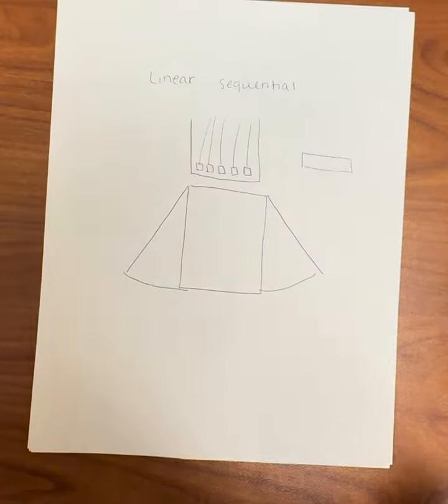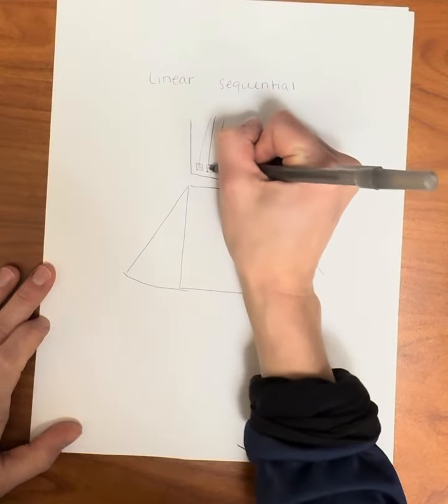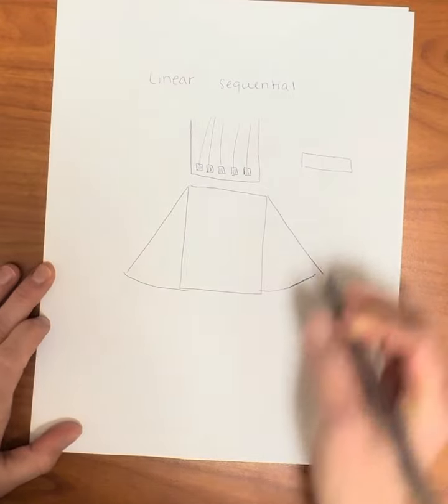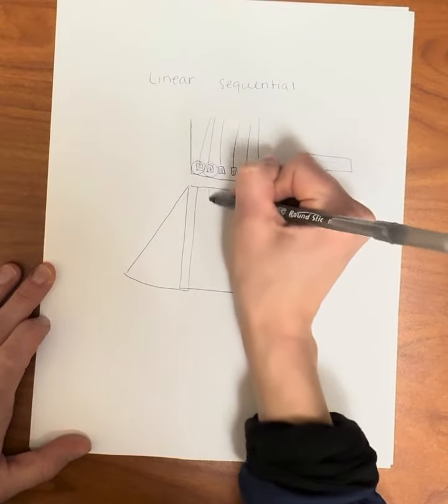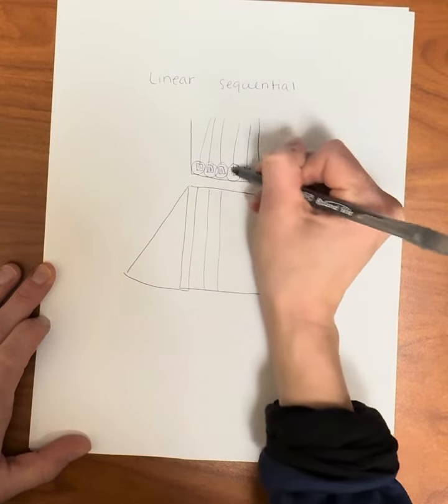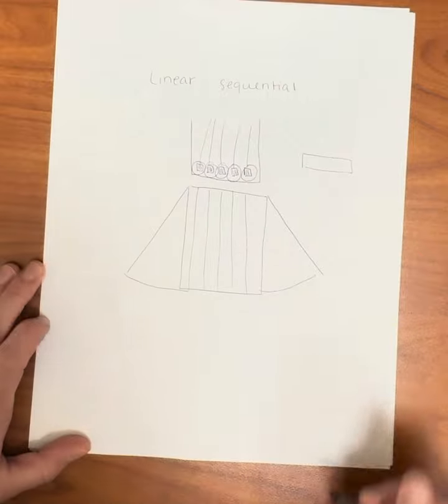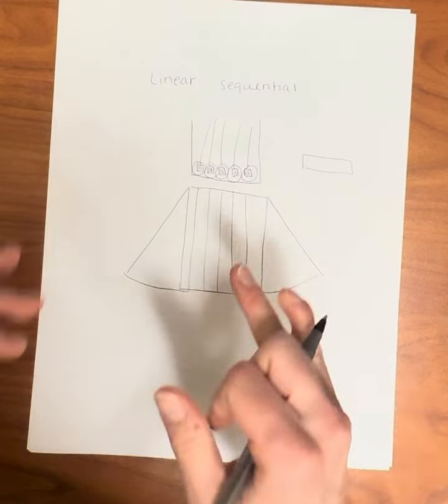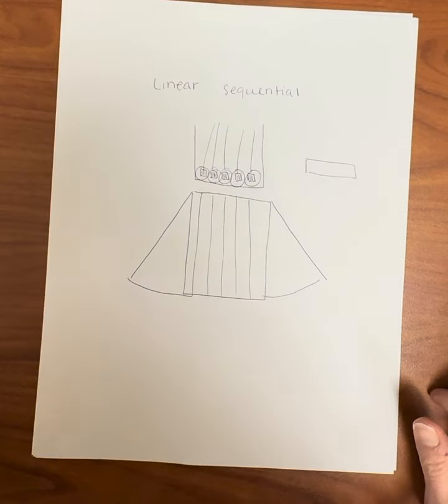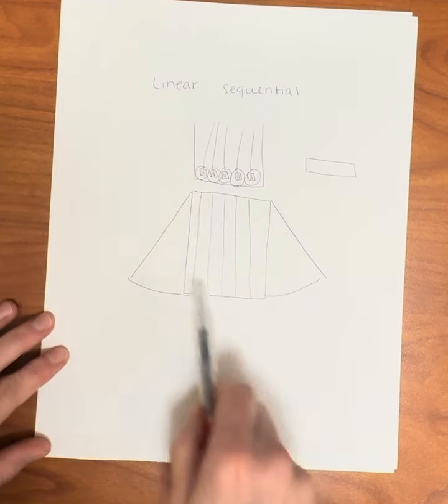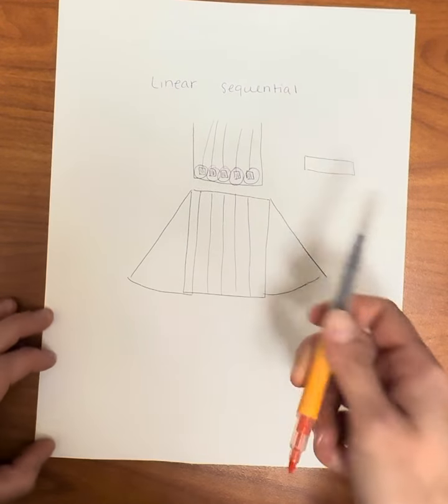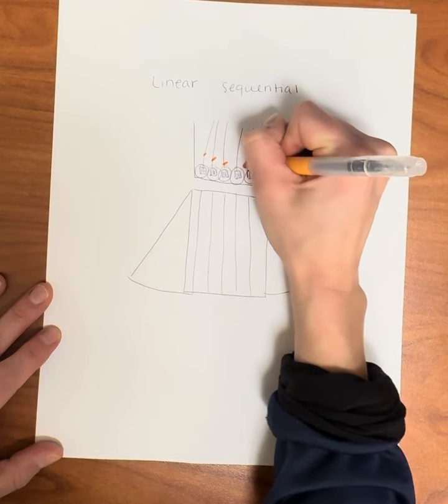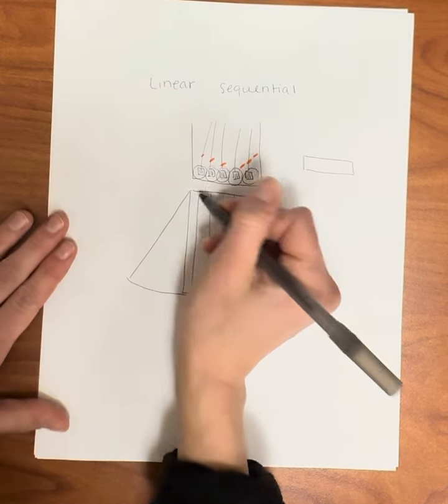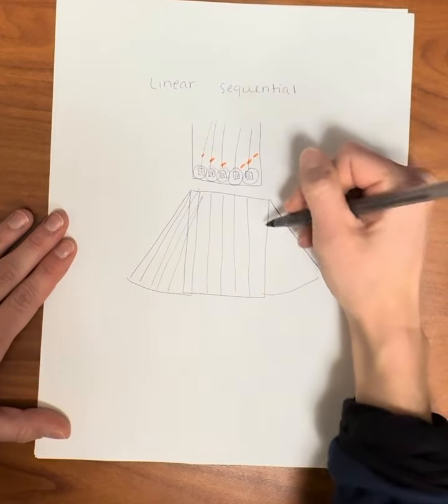Now, traditionally what happens with a linear sequential is that each element is actually a small group of elements, right? And it will zap in order. So it would zap here to get a scan line here, zap, scan line here, zap, scan line here, zap, scan line here, zap, scan line here. And that's mainly what this still does. But when it gets to the edges, it has to do a little bit of phasing. So most of our information is still gathered just by going in sequence, but we also do a time delay kind of on each side of our groups so that we get the information that's out here in the wings.